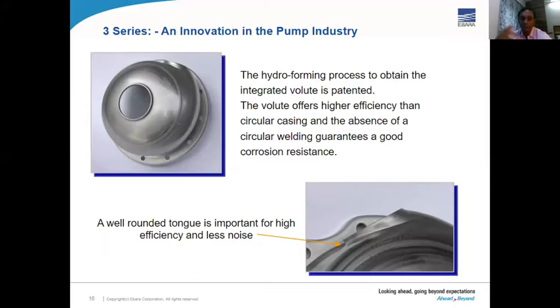We have also modified the casing to cut down on the noise level, since single stage pumps are relatively noisier than multi-stage pumps because of the volute size. So here we have made a round tongue shape on the casing side to cut down on the noise level. Since these pumps are also used on rooftops, you cannot have a noisy pump out there on the roof.